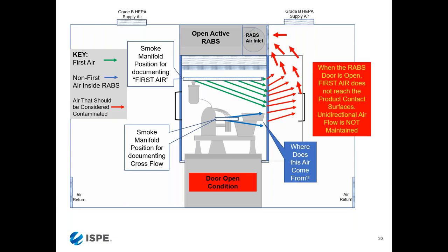If you look here, this is a manifold, near the stopper bowl. There is air going this way. There's air from the HEPA filter, top green, but there's air - where is this air coming from? That means this is a not sealed enclosure. These are things that the regulators have started seeing now.